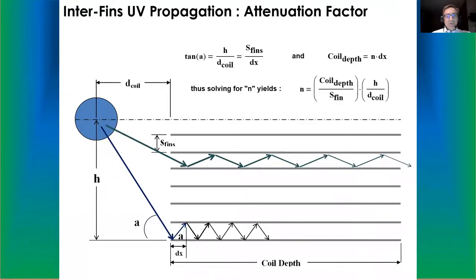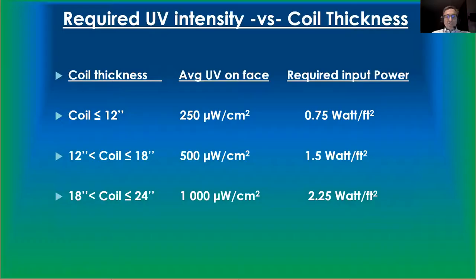It's very tiny, so we have to look at the multiple reflections inside that coil. To kill that in 1 hour, that's on the surface. Inside, it will take longer. Typically, the reproduction rate of Aspergillus niger, which is the toughest mold, is that it doubles between 1 and 3 days. In fact, you have about 24 hours, and that's what it will take to penetrate inside the coil and do its job completely. As a matter of fact, when the coil is less than 12 inches thick, which is typical, 250 microwatts per centimeter squared is sufficient. When the coil goes up to 18 inches, you want to push it up to 500. And when the coil gets to 24 inches, quite rare, you would want to go to 1,000 microwatts per centimeter squared. Most of the time, when you play around 500, you're in good hands.